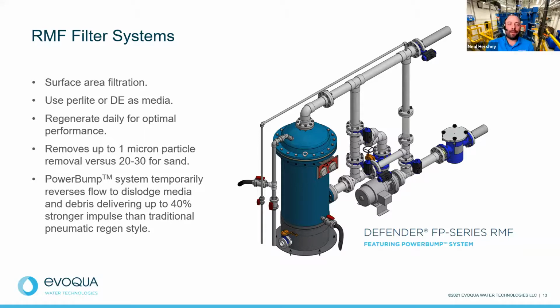This is just a quick overview of a regenerative media filter system. For those of you who aren't too familiar with that, it's surface area filtration. Sand is depth filtration; we're using a sand bed that uses the depth of the sand for filtration. Regenerative media is surface area, so it's a thin layer of perlite or DE media that coats a series of tube elements and gives you a lot of surface area for filtration. Generally it's regenerated daily for optimal performance. The big difference is that regenerative media filters down to about 1 or 2 microns, give or take, and sand is in a 20 to 30 micron range, depending on the system and the grade of sand, and there are a lot of variables there.